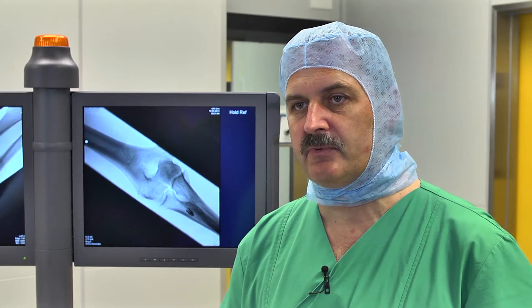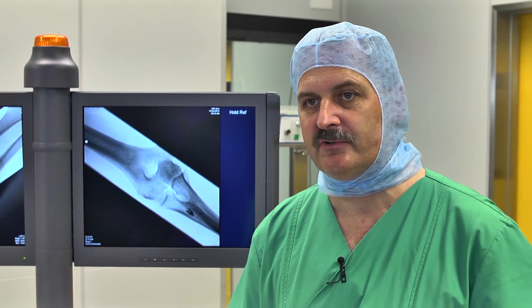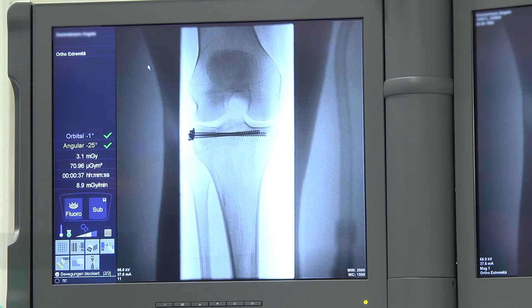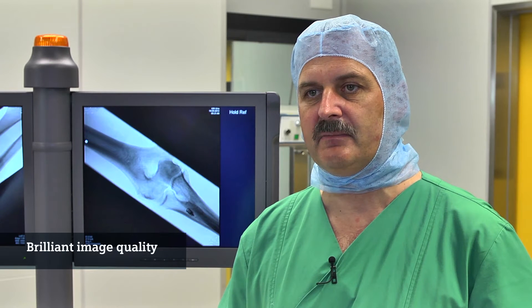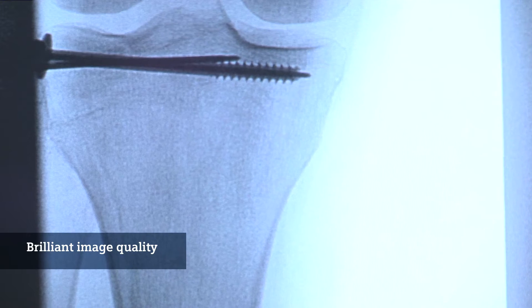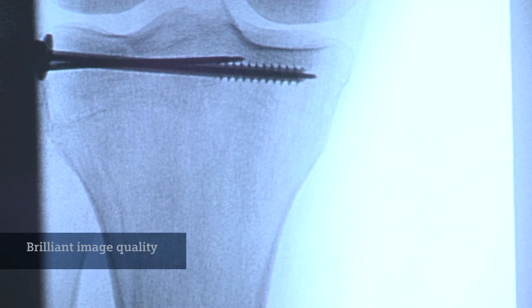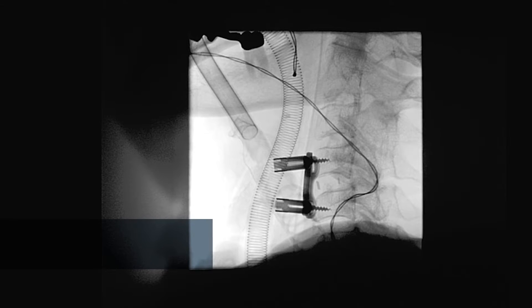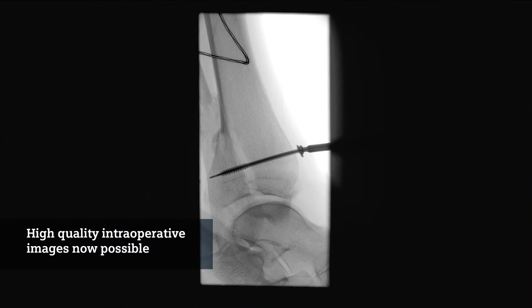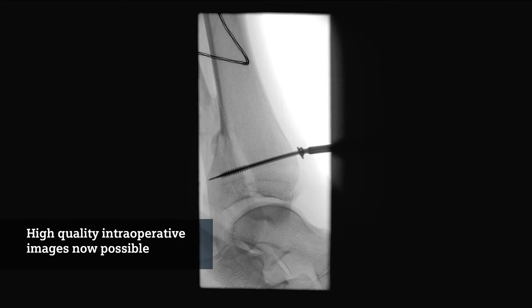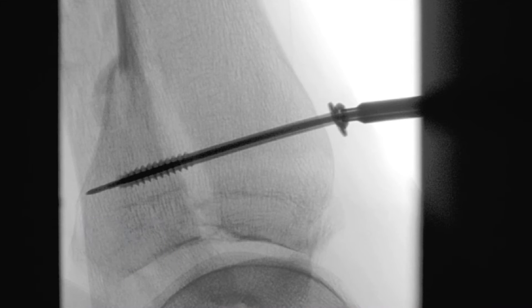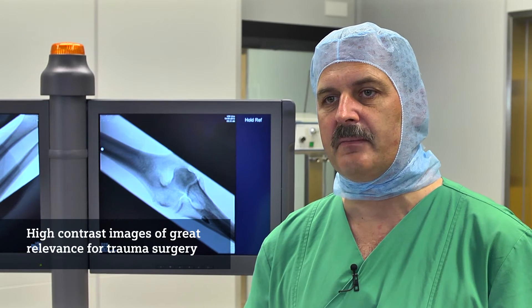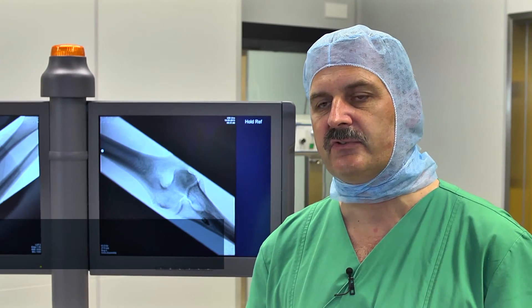As we all know, image quality depends on the amount of soft tissue or the contrast between high density objects like bone or metal. The image quality in this system is so brilliant, like in the radiology department where you just use the collimator and get nice images. So far we couldn't do it intraoperatively, but today I can get the most information out of these images. By the end of this procedure I get a very high contrast image about bony structures which I need for surgery.